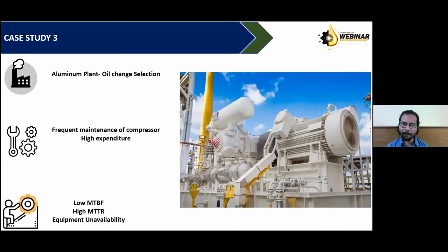May not be 100%, but 98%, 97%, at any number we choose, it will get damaged. So if we filter the oil in half of the service life, then we can extend the service life of the oil. We did it practically, and it was very successful. Definitely it needs lots of calculation before we go for such an experiment or decision.